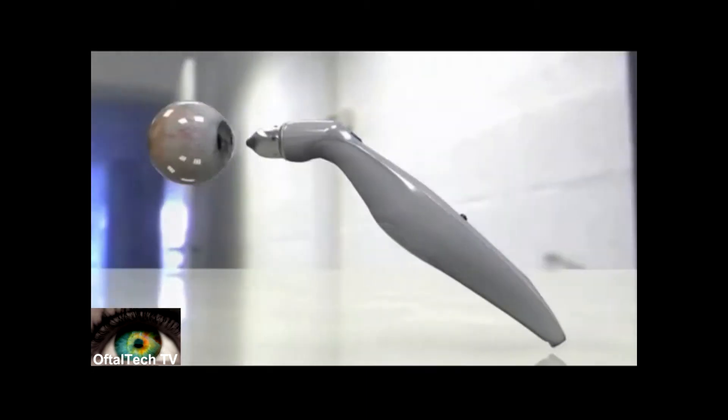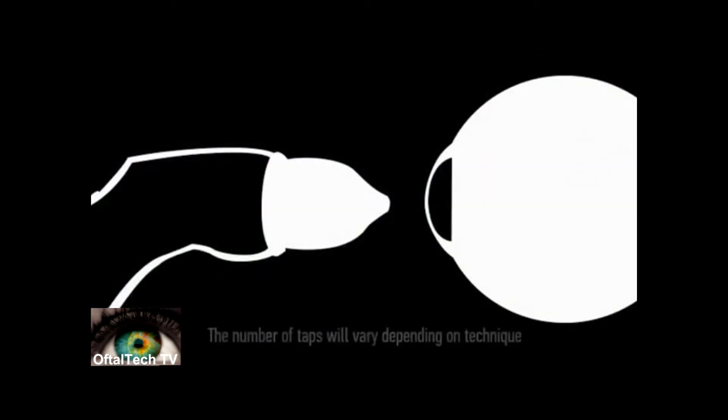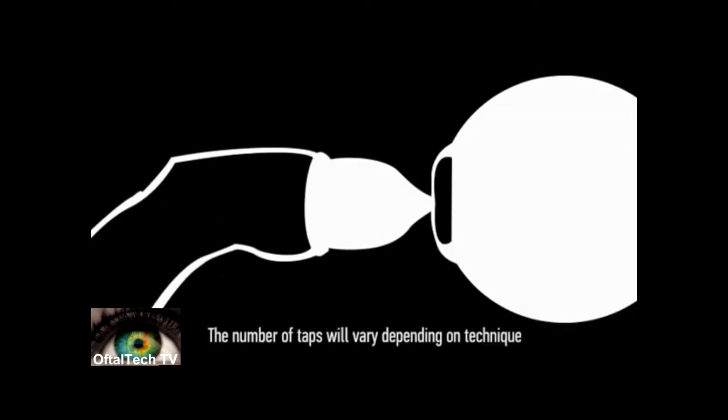After pressing the action button, the AccuPen will beep twice, indicating that it is ready for measurements. Gently tap the transducer tip on the patient's cornea. The probe should be perpendicular and measurements should be taken at the center of the cornea.